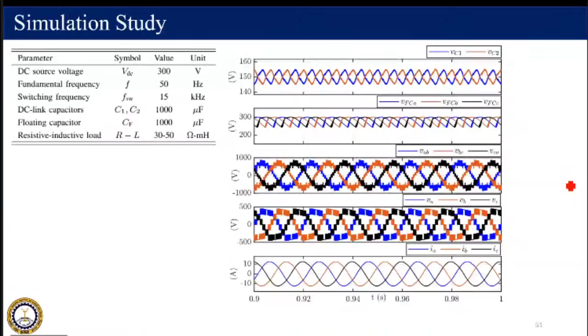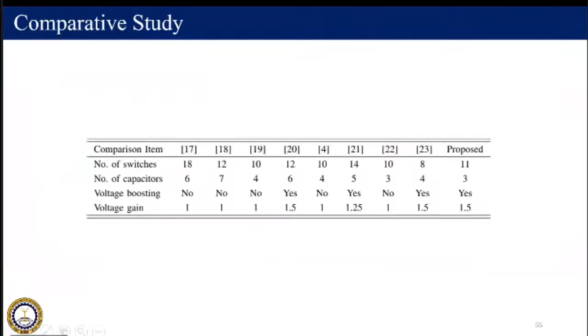These are the results showing the dynamic performance - voltage across the device and current. You can see, because of the switched current and switched capacitor, some of the devices need to carry a higher value of current; they have to withstand a higher current. So these devices have to be properly taken care of.